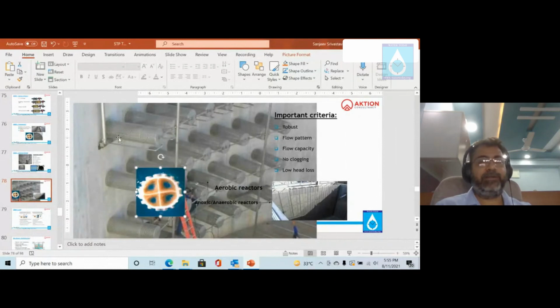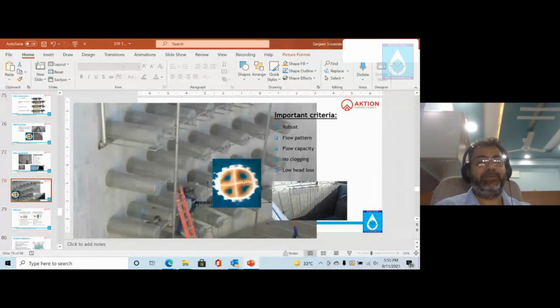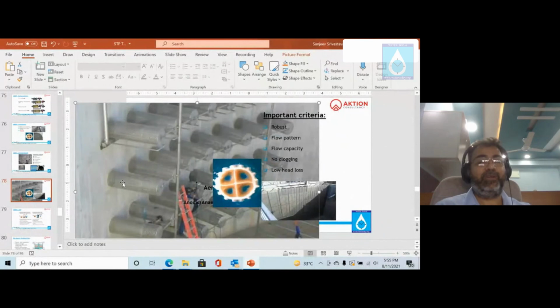After that, somewhere here from where the main water will exit, there could be some velocity. And why there is screen design, you can see there are some holes here, but then there is no hole in a whole lot of screen. Let me draw it. For some portion there is no hole, and then again there are a lot of holes. This is where a lot of know-how has gone into development of a screen over a period of time. Which kind of screen is the best design, which allows water to go, but biofilm not to slough.